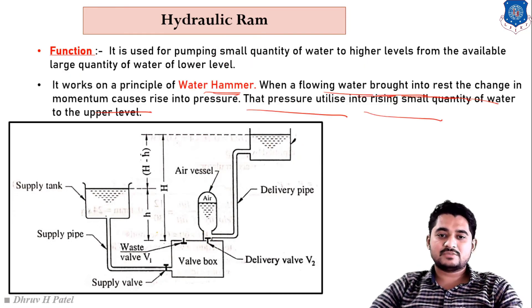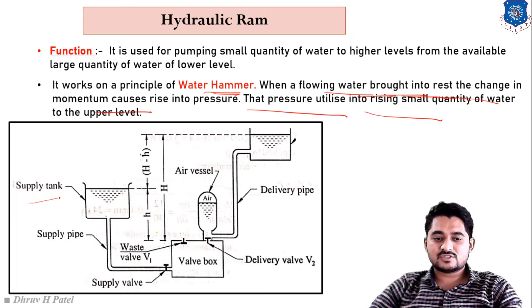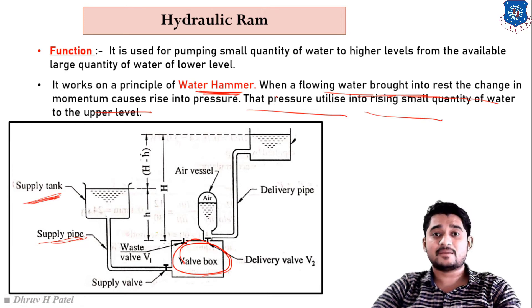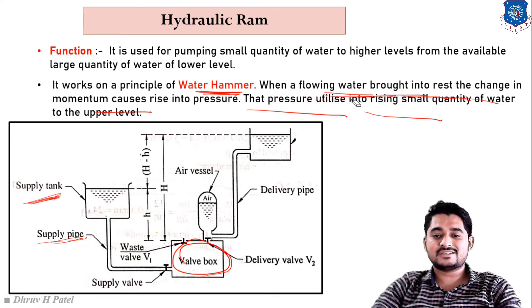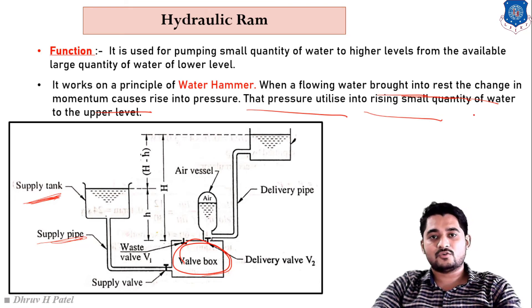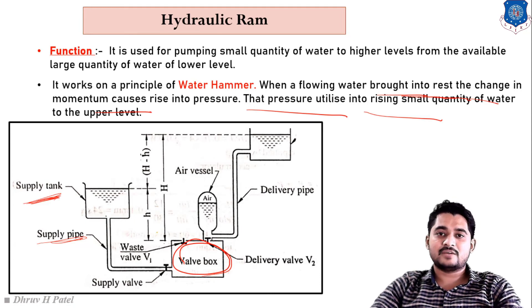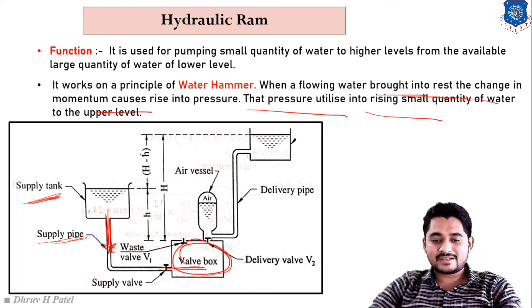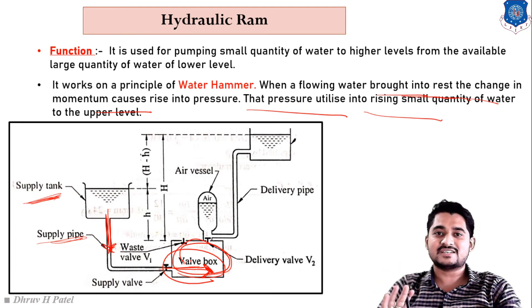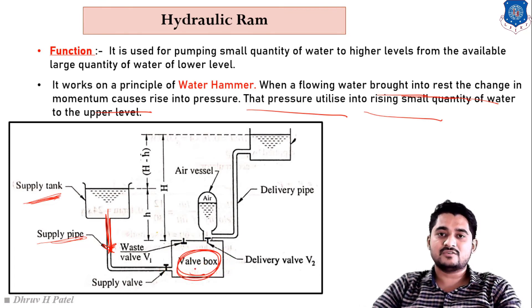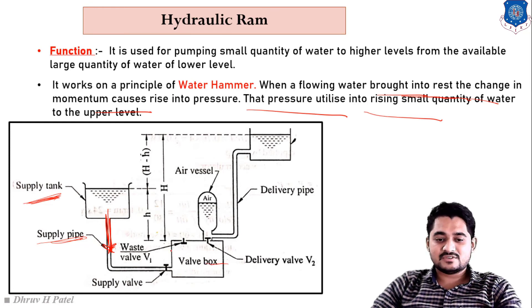In the working of the hydraulic ram, water is supplied through the supply pipe to the valve box. It works on the water hammer principle. When flowing water is brought to rest, the change in momentum causes a rise in pressure, and this pressure rise is utilized to raise a small amount of water to the upper level. Water is impacted in the valve box through a hammering process, and the momentum of water is converted into pressure.